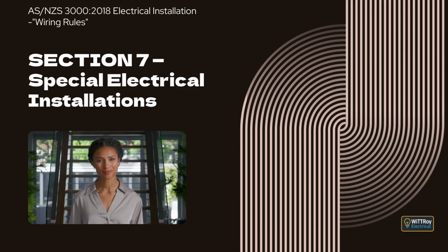Clause 7.2.10.2 Switchboards. This clause explains that an MRL switchboard must not be located in the lift shaft. It also explains that switchboards located remote from the main switchboard and dedicated to supplying individual MRL switchboards must be readily accessible and enclosed in a fire-rated room or enclosure.